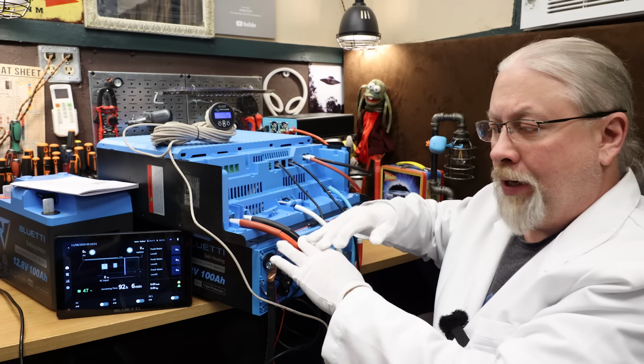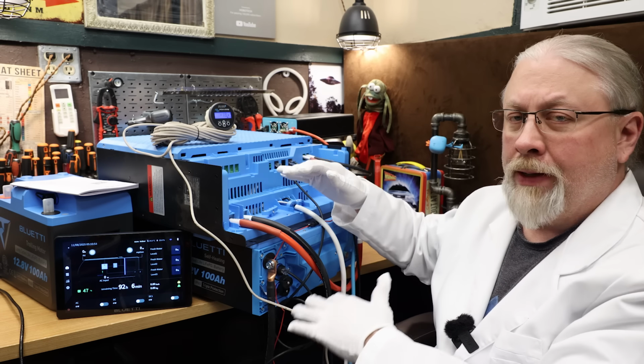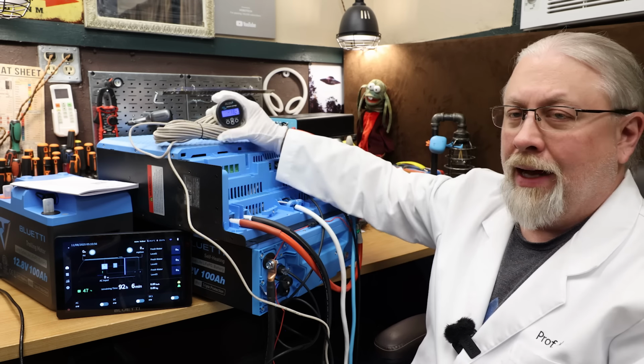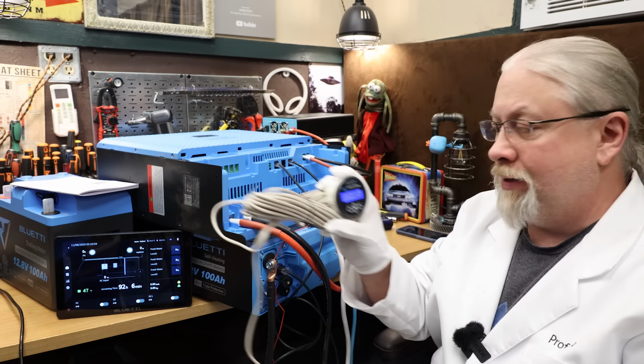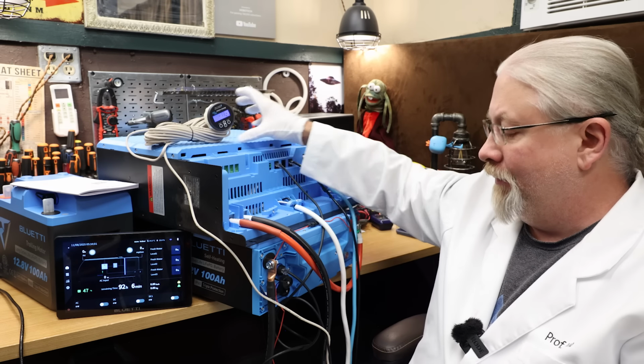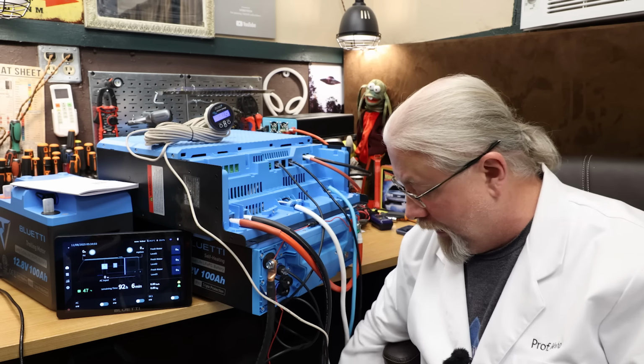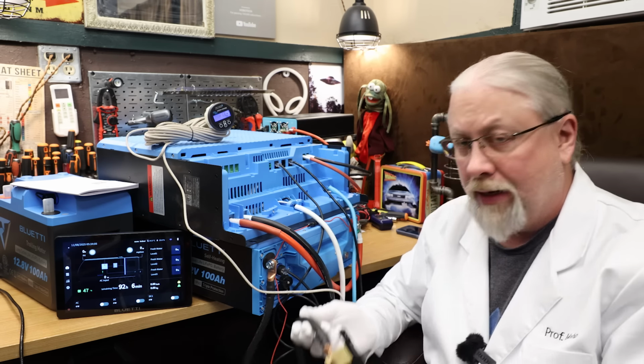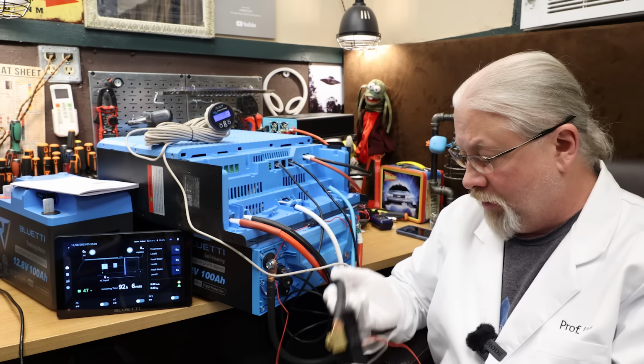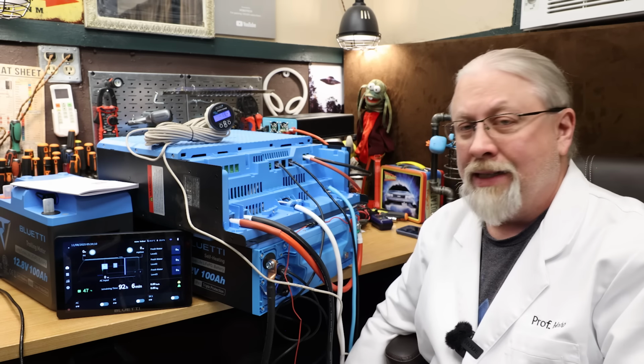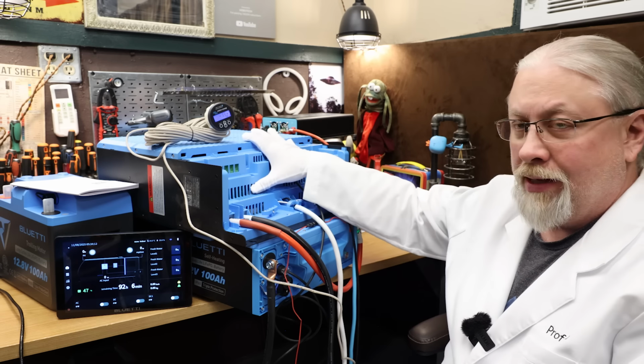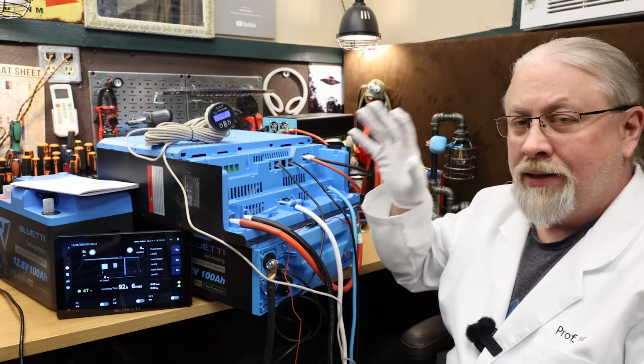So for once, we actually can separate the battery from the rest of the system, and that means I can install a Victron shunt in between the battery and the inverter, which I have right here. It is inline in the negative battery terminal, so it measures the exact wattage that this pulls under any situation.